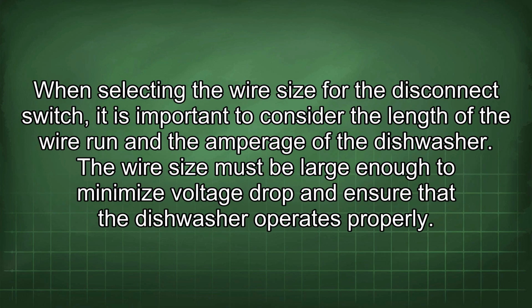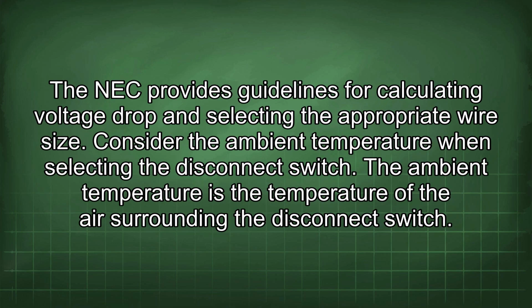When selecting the wire size for the disconnect switch, it is important to consider the length of the wire run and the amperage of the dishwasher. The wire size must be large enough to minimize voltage drop and ensure that the dishwasher operates properly. The NEC provides guidelines for calculating voltage drop and selecting the appropriate wire size.